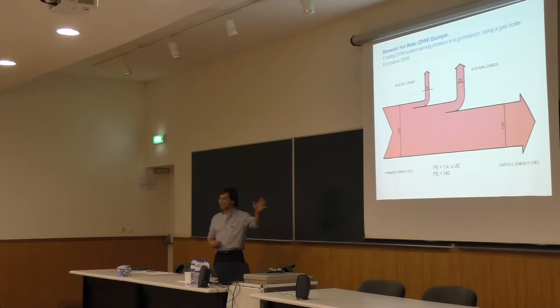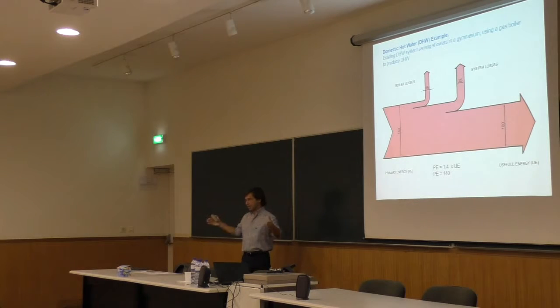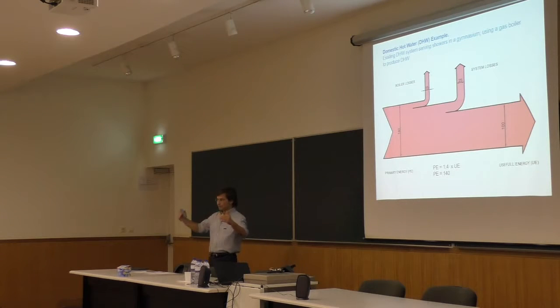11% losses, so an 89% efficient boiler on average yearly, which is a very good efficiency. It's not a nominal efficiency, it's a yearly efficiency, because there are periods when the boiler comes on and turns off. And when we have an average yearly efficiency, we always have a much lower efficiency than the nominal efficiency of the boiler. Okay? So to have 89% efficiency is actually good, in practice.